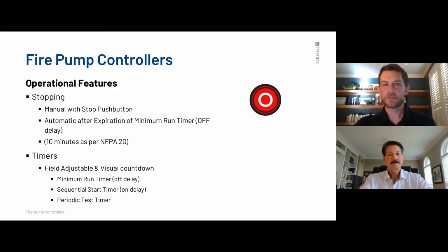Still on the operational features, stopping. Like I mentioned earlier, we come standard from the factory with a manual stop. You have the option to do an automatic stop after the expiration of a timer, which is set at 10 minutes per NFPA 20. But otherwise, your pump is going to run continuously. This goes for the electric or the diesel. If the fire pump comes on, even once the conditions are satisfied, if it's going above the cutout point that's been programmed in, the pump is going to continue to run. It's going to run indefinitely until somebody comes in and manually stops it.